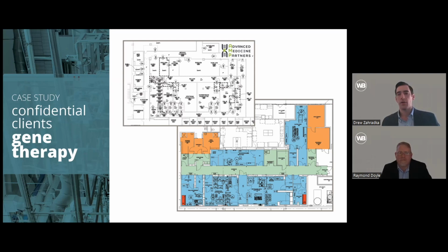So earlier we talked about flow of air through clean room spaces, but there's also the flow of materials and personnel. So in this top left instance for AMP, the materials flow through the supply corridor, out through downstream, and through the production suites, and then out through the return corridor before they exit the clean room suite. Whereas in the bottom right, you have a common corridor to an airlock to each clean room suite. And in this instance, materials and personnel flow in and out of the space in the same pathway. So what you would do here is you'd make sure that all of your waste is sealed and all of your clean samples are sealed prior to entering that common dirty corridor.